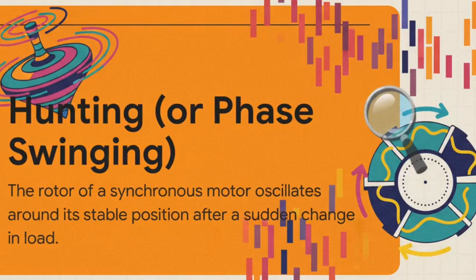The second big headache, especially true for precision synchronous motors, is called hunting. The best way to picture it is like a spinning top that suddenly starts to wobble. That's what's happening to the motor's rotor. When the load on it changes out of nowhere, the rotor doesn't smoothly settle into a new position, it overshoots, swings back, and oscillates around where it's supposed to be.